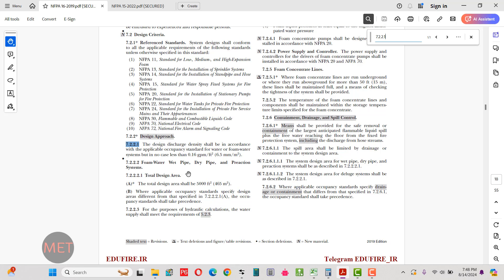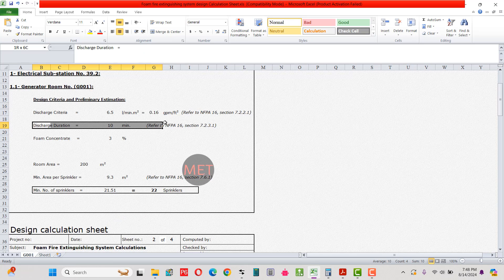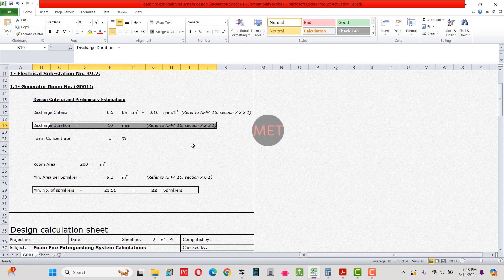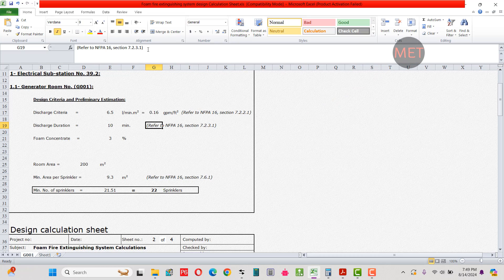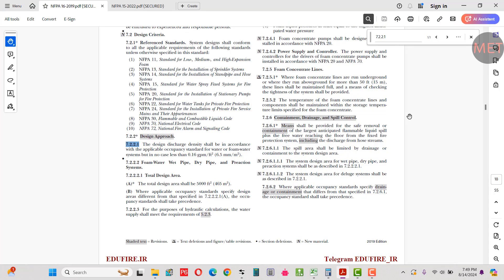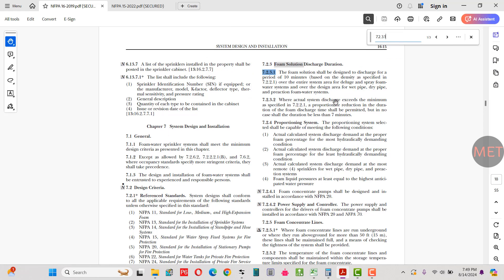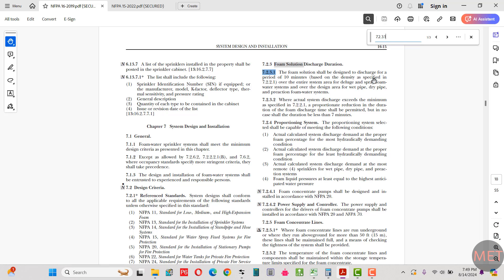The next input is discharge duration, per NFPA 16 section 7.2.3.1, which states the foam solution shall be designed to discharge for a period of 10 minutes based on the density specified in section 7.2.2.1. So we've selected a density of 6.5 liters per minute per square meter and a discharge duration of 10 minutes.